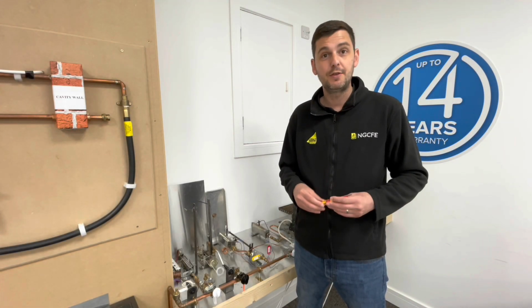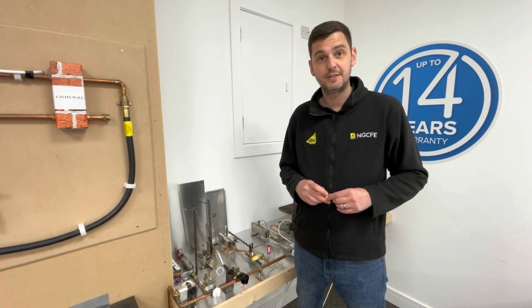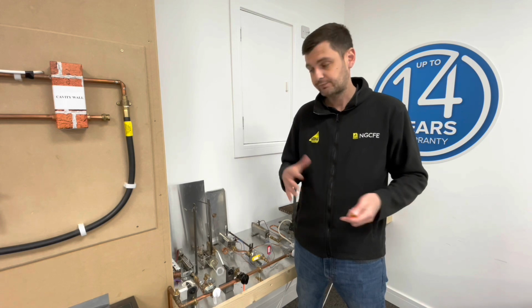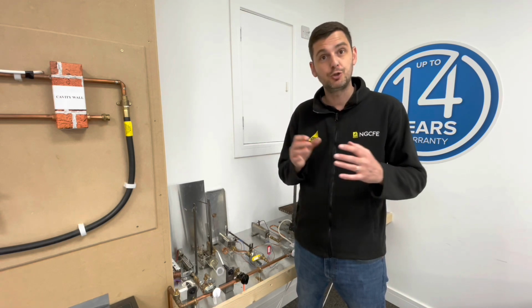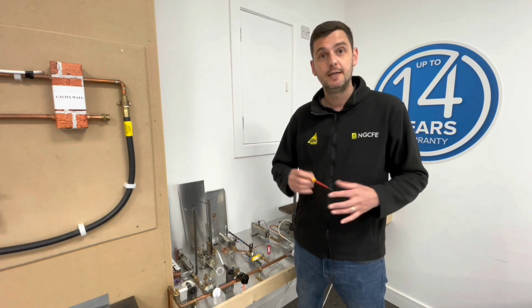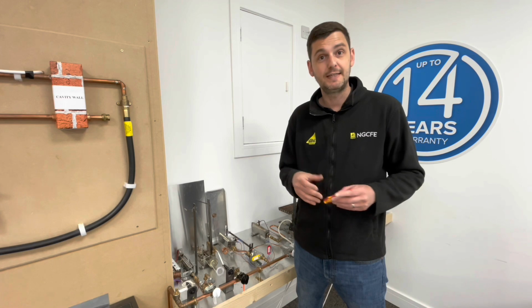So the first control we're going to look at is a liquid expansion thermostat with thermoelectric FSD. So this is a more modern type of oven setup. And what we've got is a liquid expansion thermostat, which is the thermostat at the top of the oven, which monitors the temperature within the oven and adjusts the flow of gas to suit. And then we've got a thermoelectric valve, which is the FSD.